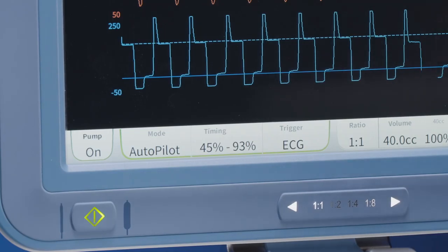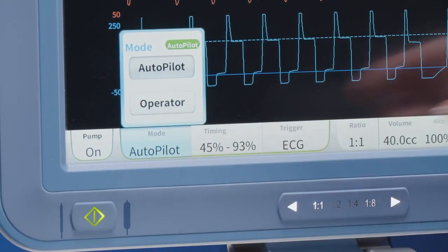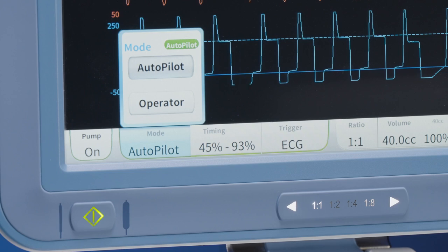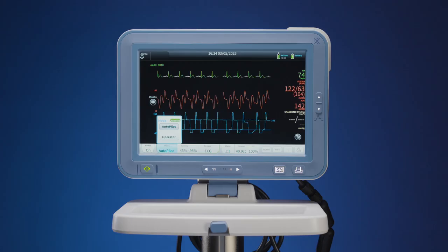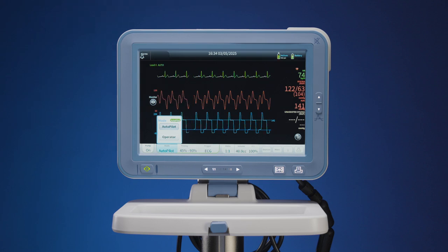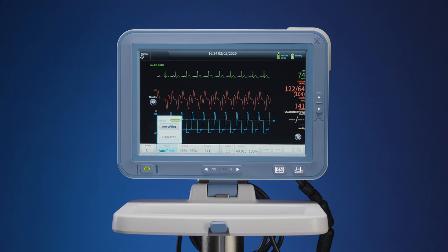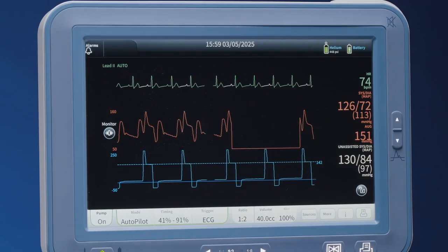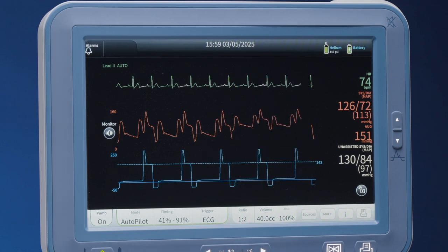In autopilot mode, the user can change ECG leads, sources, and gain control. However, autopilot mode will automatically change the ECG leads and source to maintain optimal IABP therapy as needed. The default lead is lead 2 when ECG input is chosen. The arterial pressure signal may come from a variety of sources: the high-fidelity fiber optic sensor, transducers, or from monitors.